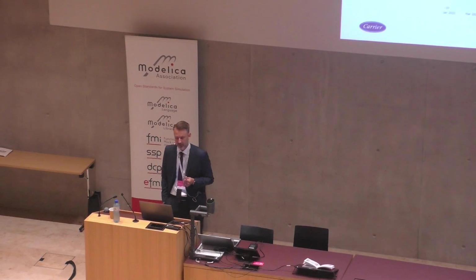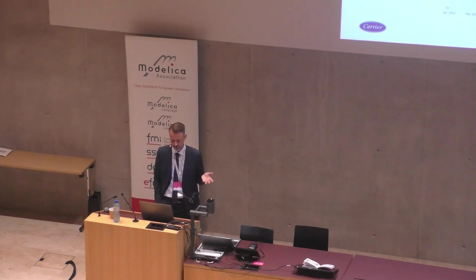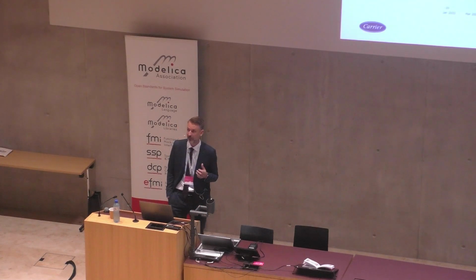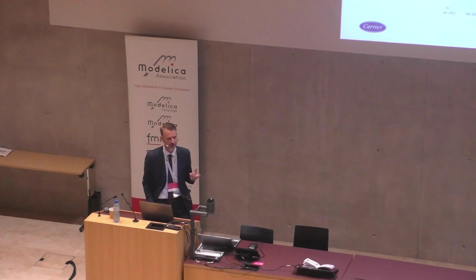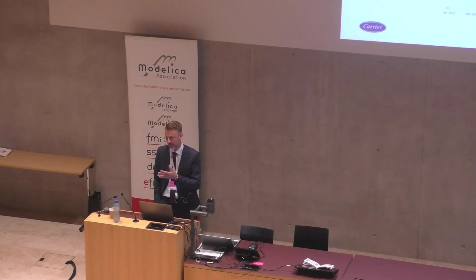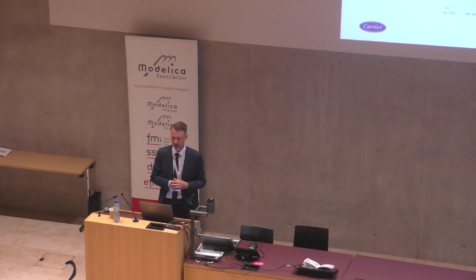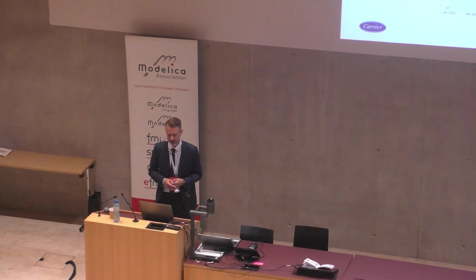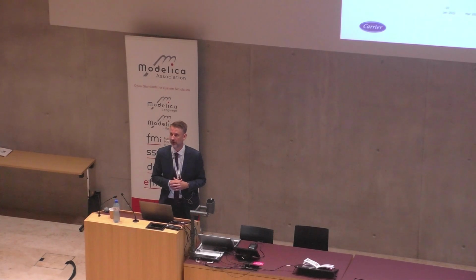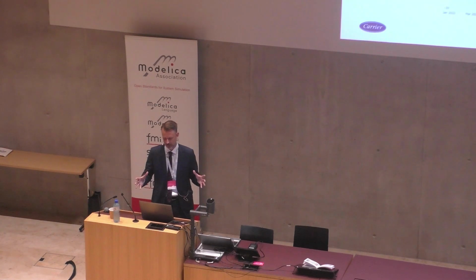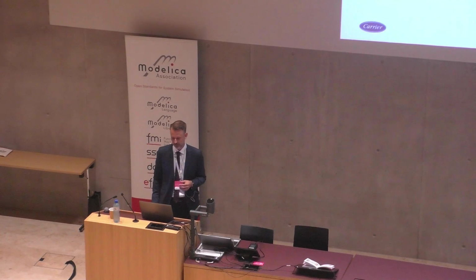And we defined a few cases: constant load, 25, 50, 75, 90%. Data centers very often run at part load conditions. That's good news, right? Because then we have more degrees of freedom to optimize. And we had some varying load to see how the system reacts to varying loads. And then we picked 8 locations. Our sales team thought these were particularly important to study. So we pulled weather data, relative humidity and temperature off the web. And again, we turned the crank. In this case, our methodology was unit commitment. So we solved a discrete unit commitment problem. We got all our chiller curves and all the pump curves in the models. And then we looked at what the solutions look like and how much we can save.